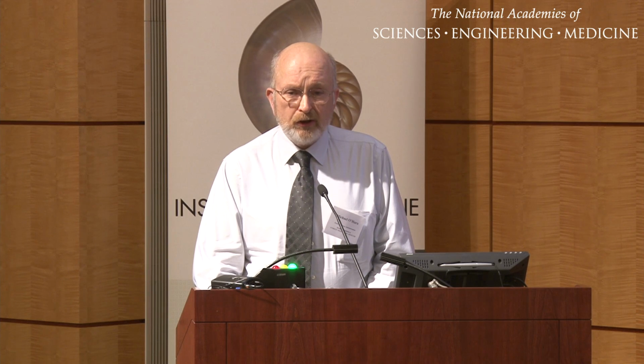So we have to take a bit of a step back, and I'll just tell you a little bit about device classifications. Class 1 devices are the lowest risk devices. They're subject to general controls. The general controls are registration and listing of the device.